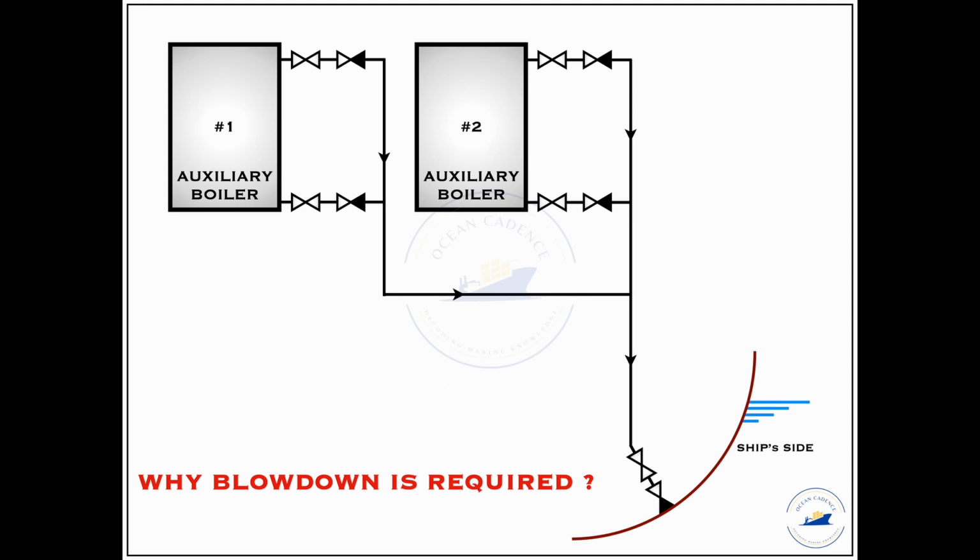So now when this dosing occurs, first of all during the evaporation and the subsequent condensation in the condenser system and thereafter the cyclic process, what happens is that a certain amount of precipitation of lighter as well as heavier salts occurs within the steam system where the evaporation is occurring, that is inside the drum. So these salts, whether it may be temporary hardness inducing salts or the permanent hardness inducing ones, that is the lighter salts or the heavier salts, what they do is they separate out from the system and they settle down. Either they settle down or they float up, but basically they get separated from the system.